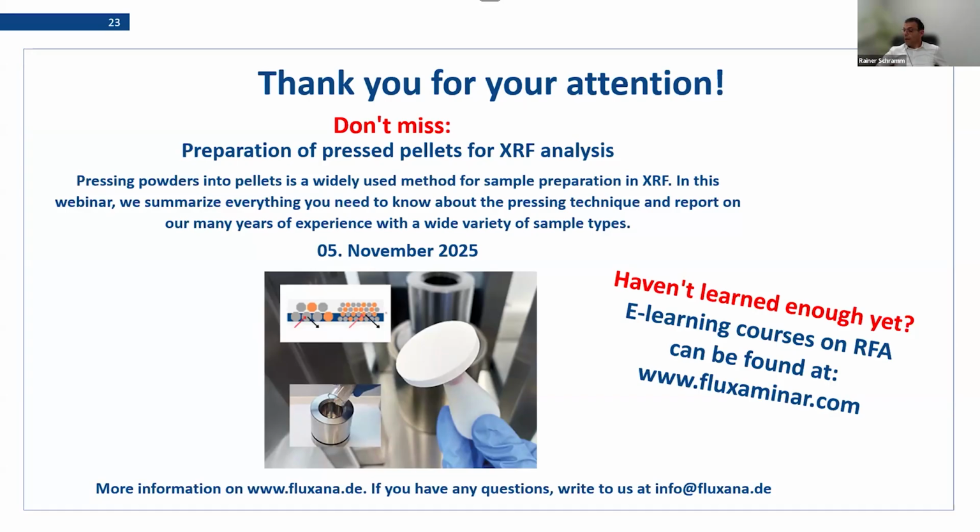More questions? Line library, how does it work? Of course, this is a bit different from manufacturer to manufacturer. But normally I would perform this in the following way: you have your application. The application has, of course, the line selection, and the application normally allows you to establish on these settings a drift correction measuring setting, which sometimes is just the same settings and the measurement times are just, for example, doubled or measured 4 times.